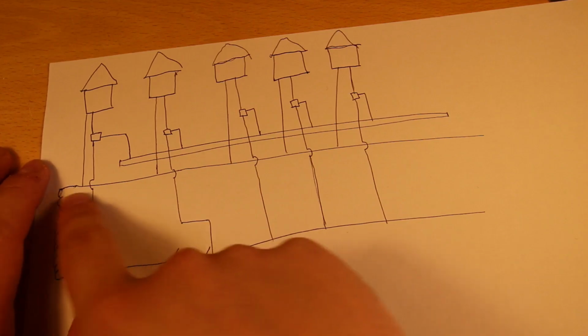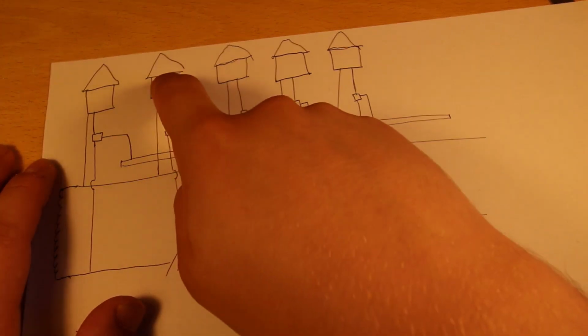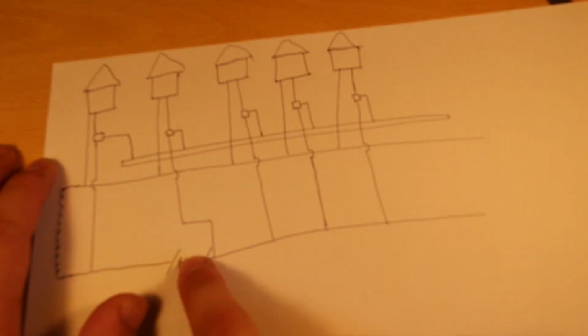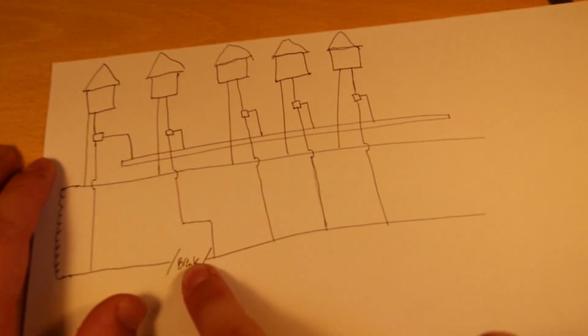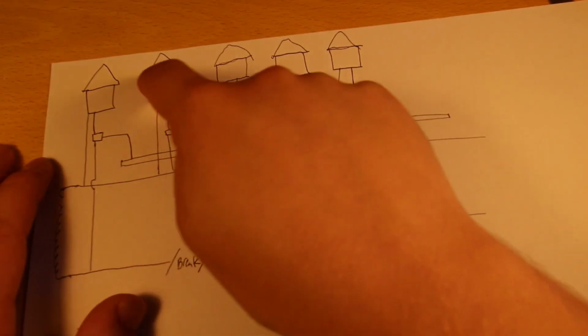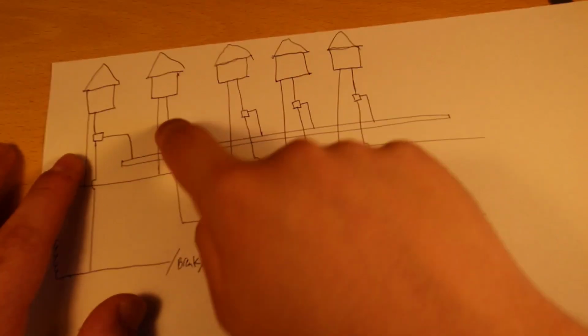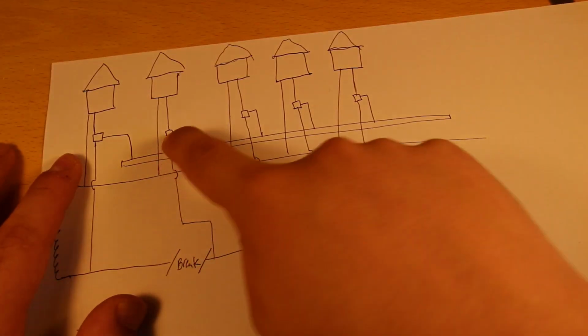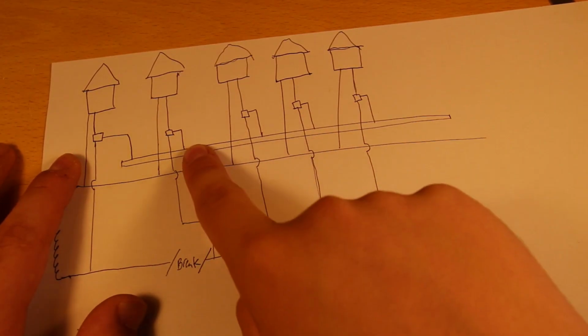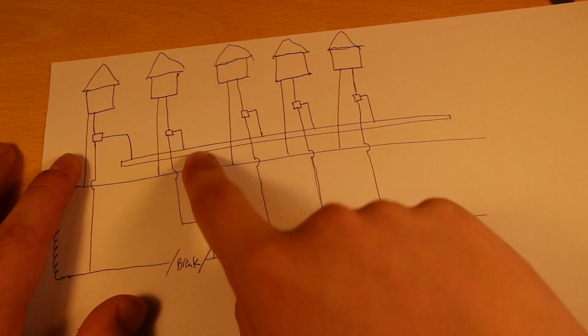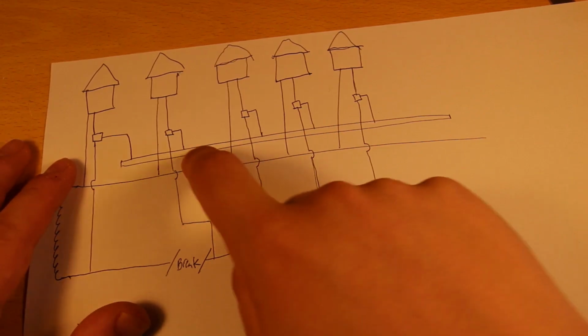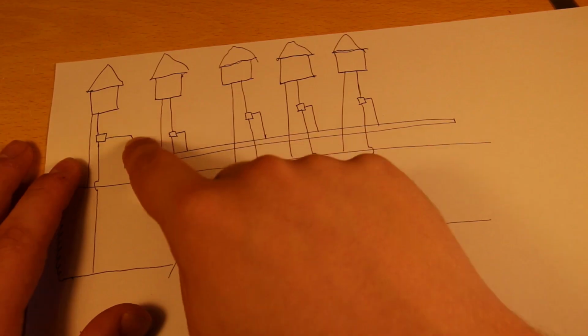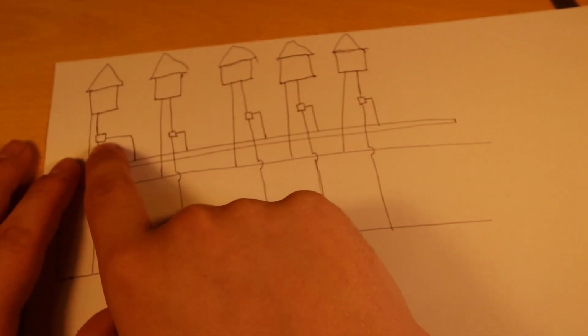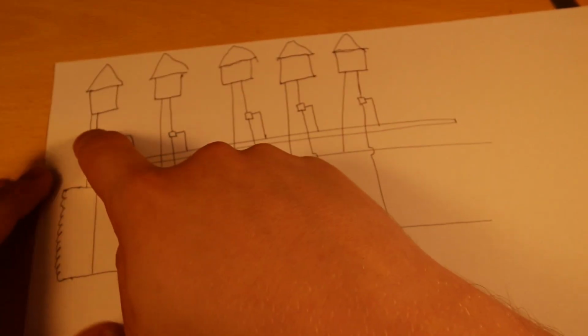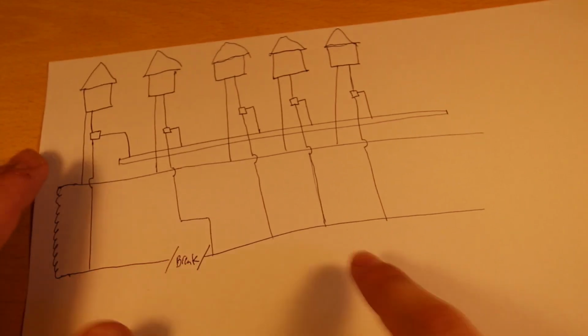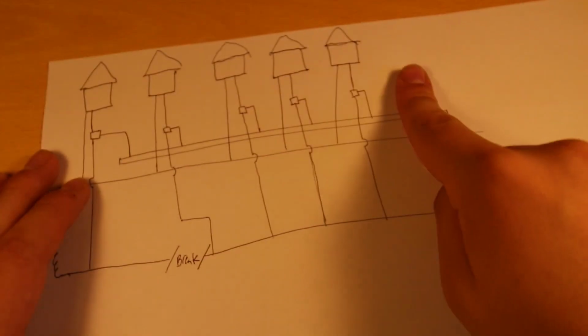In the next house, it comes along, up the live, through the load, down the neutral, and it can't get back because it's broken. So what will happen is, it will come up the live, go through the load here, down through the neutral earth link in the service head, down the bonding cable, into the water main or gas main, through the pipe, back up the bond cable on the main in another building, through the link and down to neutral. And the same thing will happen with all of these houses here.